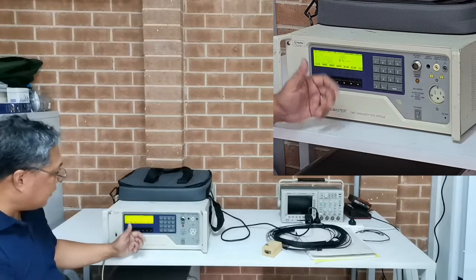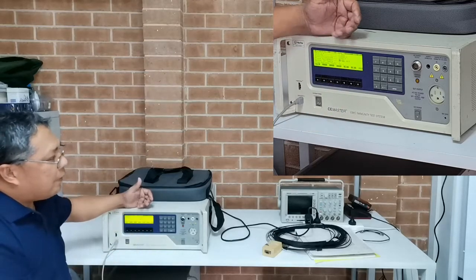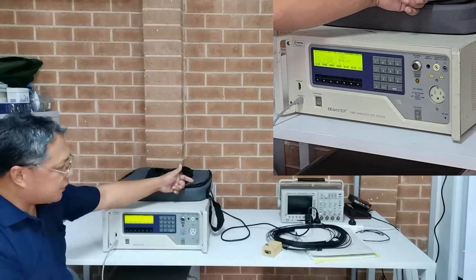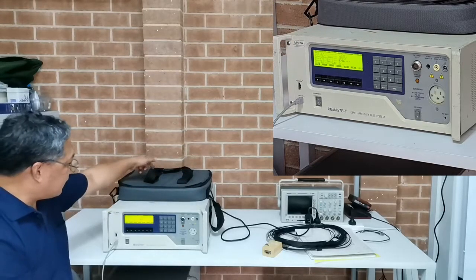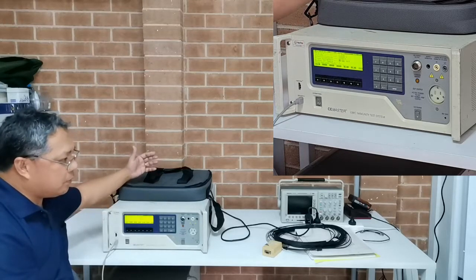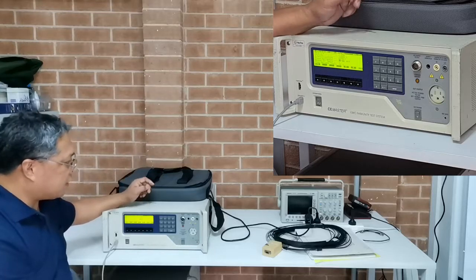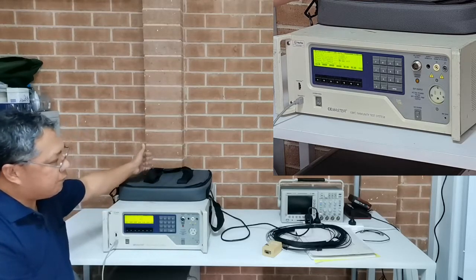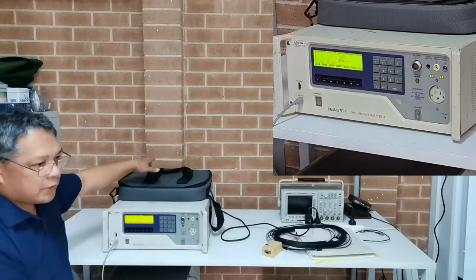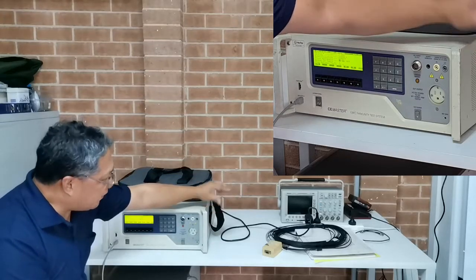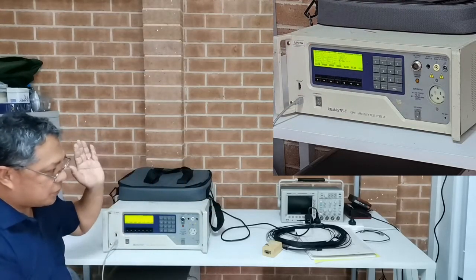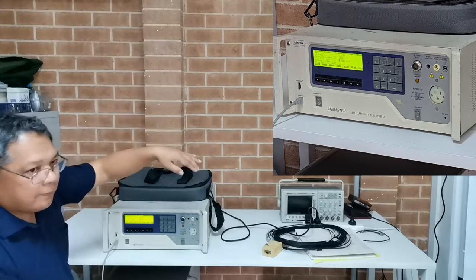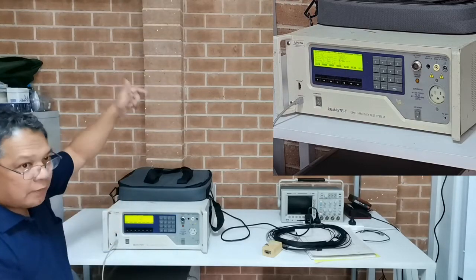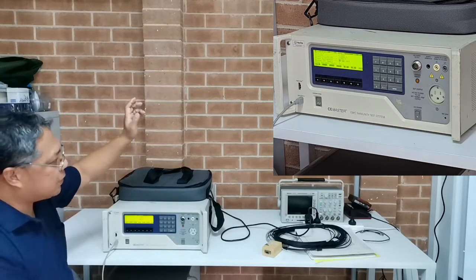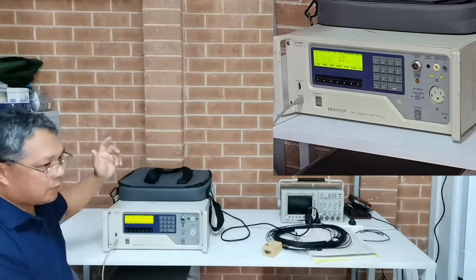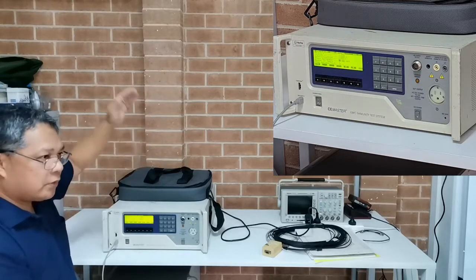So for the angle degree, and again, how do you apply the phase reference? I have to use the mains input here with 110 volts AC as a reference, but that down-converted mains into the EUT reference must be the same phase as the one that goes to the decoupling network as well. So in order to synchronize the surge spike to the phase that you want, let's say you want to apply 90 degrees, it must be on the top of the phase of the mains. So you have the surge going on the top, or if you go negative 1 kV, it goes downwards on the top of the sine wave.